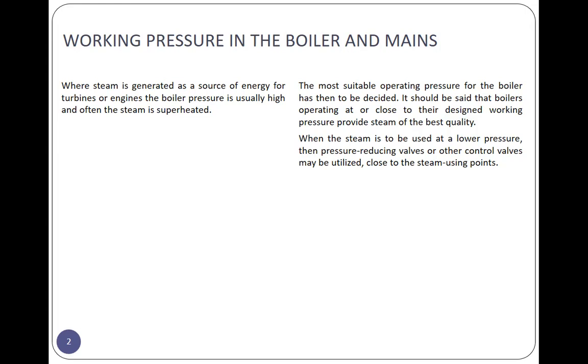So when the steam is to be used at a lower pressure, then pressure reducing valve or other control valves may be utilized close to steam using points. Yan, yung mga reheat coils, yung mga steam na plancha. So kailangan mababa ang pressure niya.